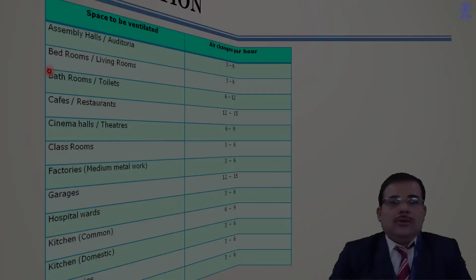Depending upon the type of building, the number of air changes per hour is regulated. In case of assembly halls or auditoria, where more people will be accommodated, 3 to 6 air changes per hour are expected. In such circumstances, it is mostly not possible to achieve this naturally, so we need to provide an air conditioning system or air freshening system. In case of bedrooms and living rooms, it is again 3 to 6, but in case of bathrooms and toilets, the air change cycle needs to be maintained at 6 to 12 cycles per hour.